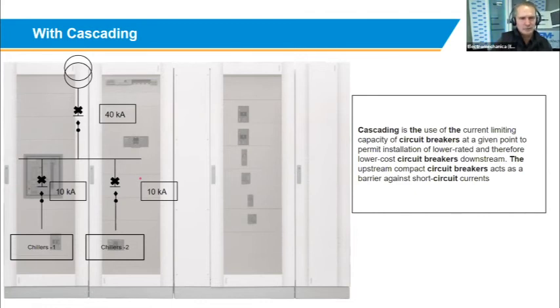Keeping in mind that when you do a cascaded board, there must be a label on the board saying that it's a cascaded system. And when it is a cascaded system, you're not allowed to change a product inside that board with something else than the product that you take out. So you cannot take a Hager product out and replace it with a Chint, Schneider, whatever, any other manufacturer. That is actually illegal, because as soon as you do that, you lose your cascading capability. And I'll show you in the next slide what can happen if something like this does happen.